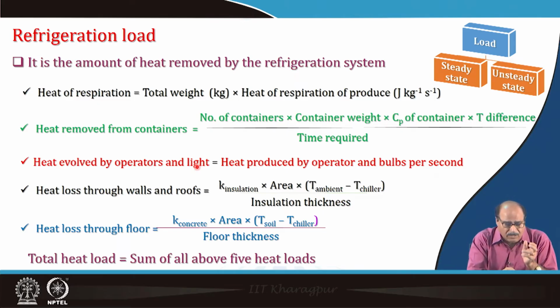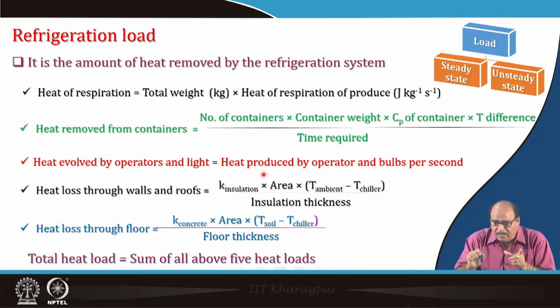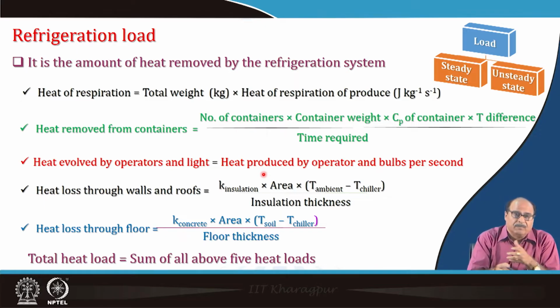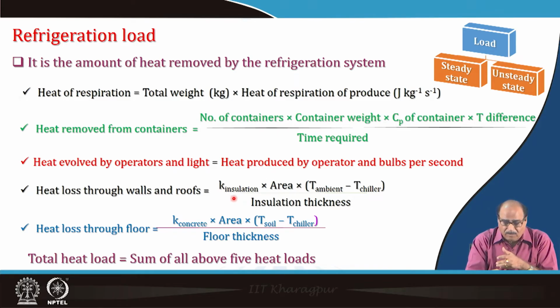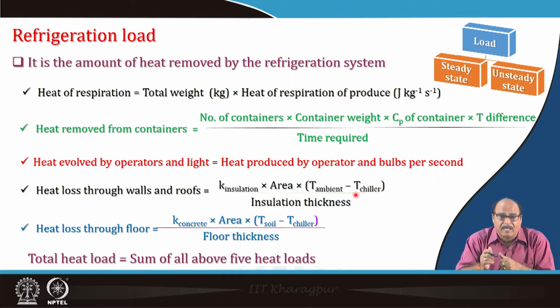Heat evolved by operator and light equals the heat produced by the operator and the bulbs per second. Then there may be some heat loss through the walls and roofs, calculated by thermal conductivity K of the insulation multiplied by area multiplied by temperature of the ambient air minus temperature of the chilled air, the whole thing divided by insulation thickness. This gives the total heat loss through the walls and roofs.